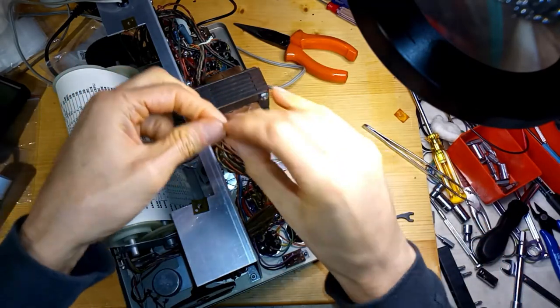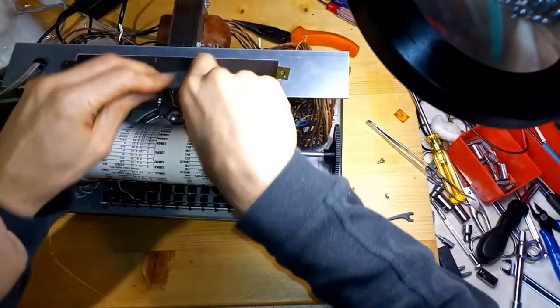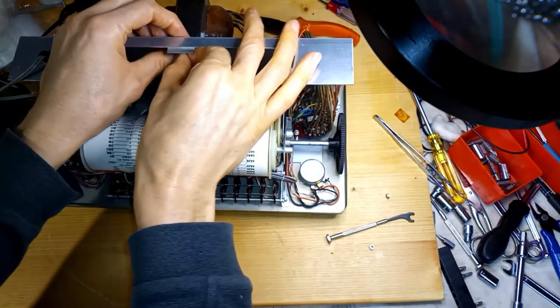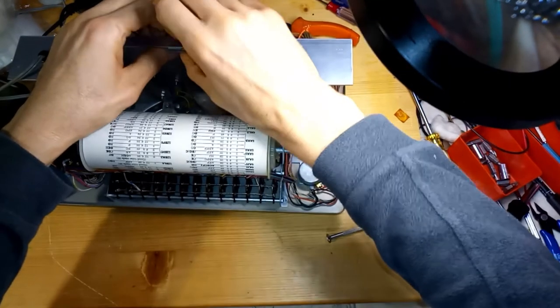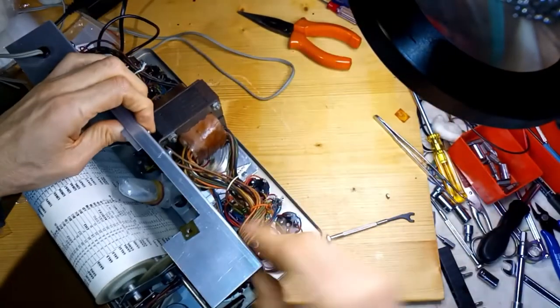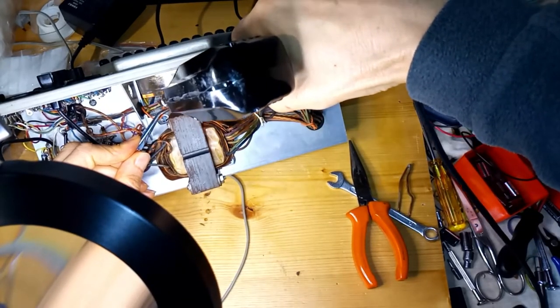The pilot lamp bracket is the first thing to be removed to access the meter, and also the last one to be put back in place when the meter is reinstalled. Of course, the electrical connection of the meter should not be forgotten.